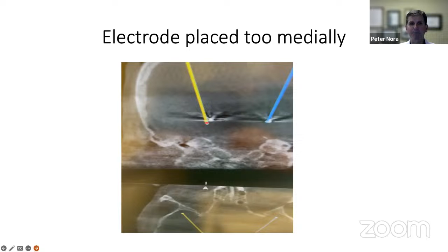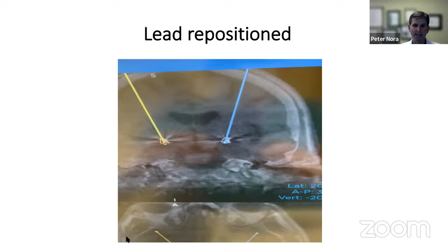In this next picture, I've moved the lead 2.5 millimeters, and I can superimpose my MRI scan over that to show me that now I'm within a reasonable range, and I feel my electrode is in a position where it should be acceptable based on my plan. The time between placing my first, right side electrode, the yellow, getting my O-arm spin, and replacing it is about 8 minutes. If you compare that to closing up the patient, going back to the CT scanner, and coming back to the room, obviously we're talking about major time savings, which adds to safety and efficiency.